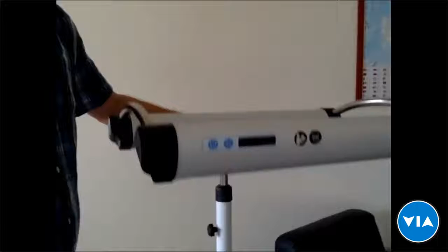So what is innovative about this device is that you don't have to adjust the angle, because we have two canopy arms that allow us to use the warmer overhead unit directly on top of it, which doesn't obstruct the heat wave, and it doesn't remove the efficiency when the device has to be used together with a radiant warmer. It is a really important feature, requested a long time ago by our partners, and they found it very, very useful. And the babies that are underneath radiant warmers are treated equally efficiently to the ones that are under without any warmer, and they can be treated as a standalone unit.